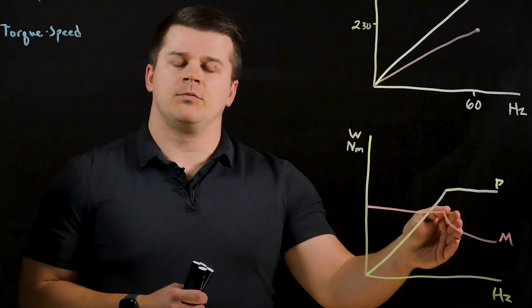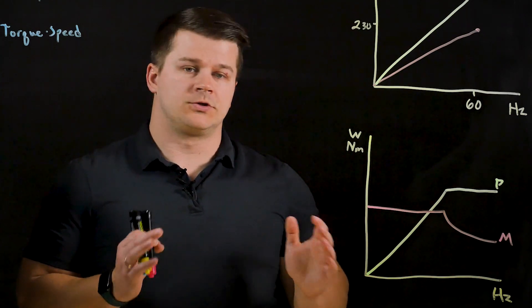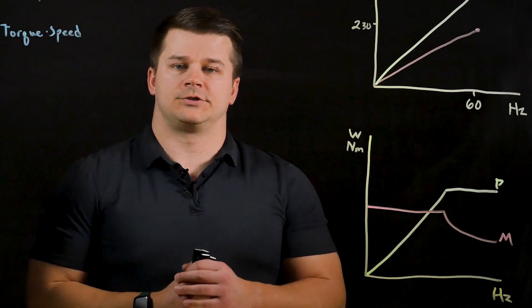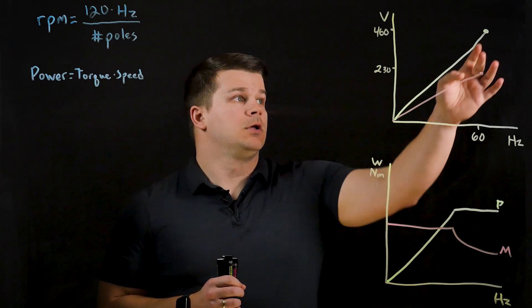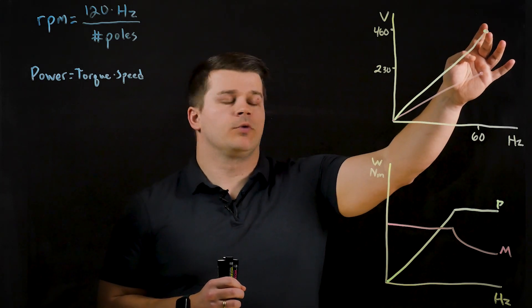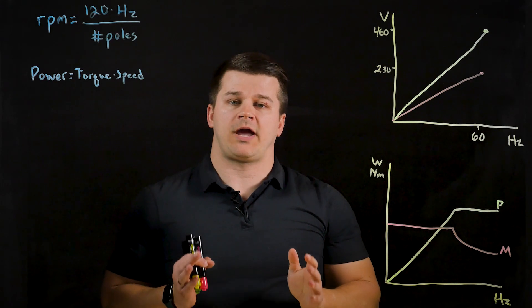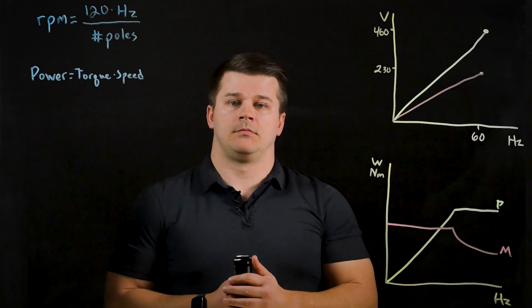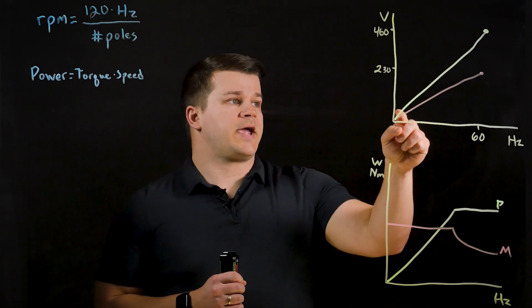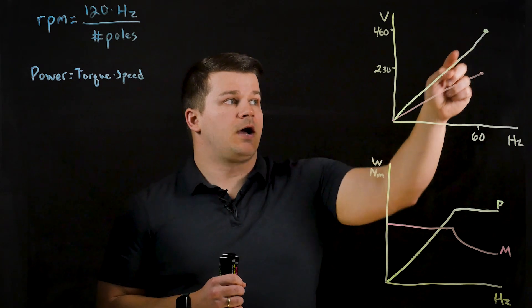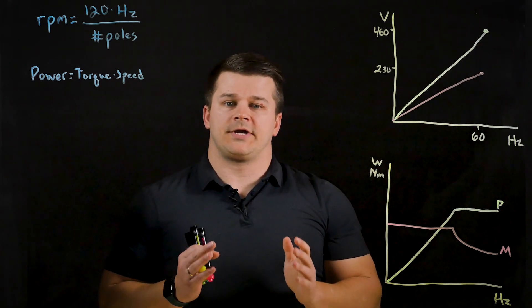Beyond the rated frequency is the field weakening range where the torque drops off and the motor characteristics change. With a traditional line-fed motor you're outputting the rated frequency and voltage to achieve the rated torque at full speed. By utilizing a VFD you can choose any frequency on this line and achieve the rated torque of the motor at your desired speed.